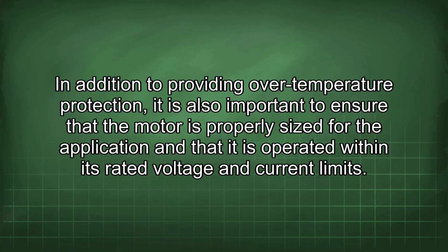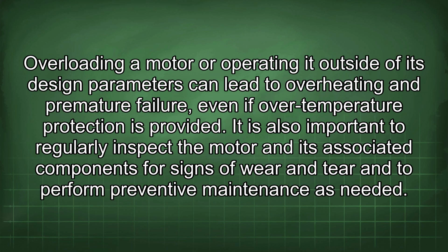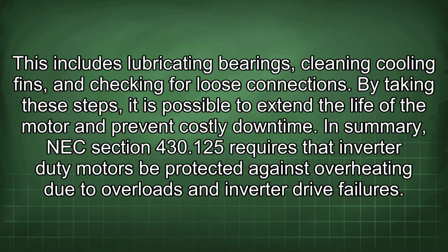In addition to providing over-temperature protection, it is also important to ensure that the motor is properly sized for the application and that it is operated within its rated voltage and current limits. Overloading a motor or operating it outside of its design parameters can lead to overheating and premature failure, even if over-temperature protection is provided. It is also important to regularly inspect the motor and its associated components for signs of wear and tear and to perform preventive maintenance as needed. This includes lubricating bearings, cleaning cooling fins, and checking for loose connections. By taking these steps, it is possible to extend the life of the motor and prevent costly downtime.